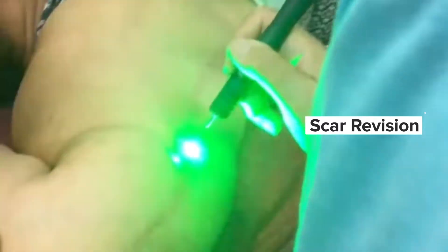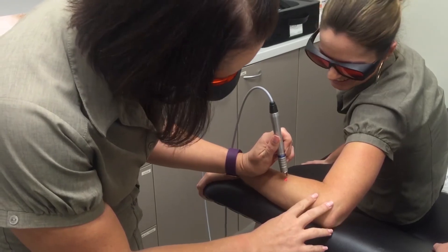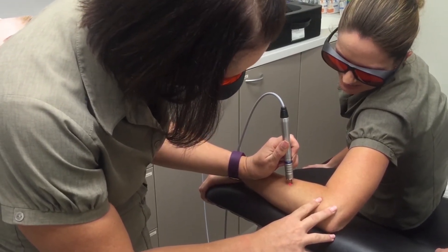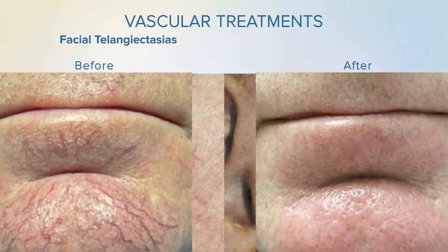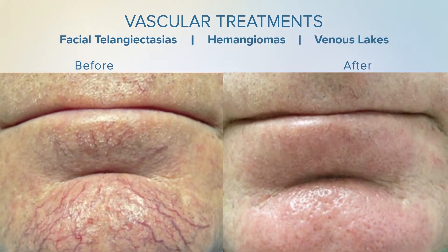Using the principles of selective photothermolysis, the 532 nanometer wavelength is preferentially absorbed by oxyhemoglobin and melanin for predictable lesion removal without purpura or bruising. Vascular treatments performed using Dermalight include the removal of facial telangiectasias, hemangiomas and venous lakes.